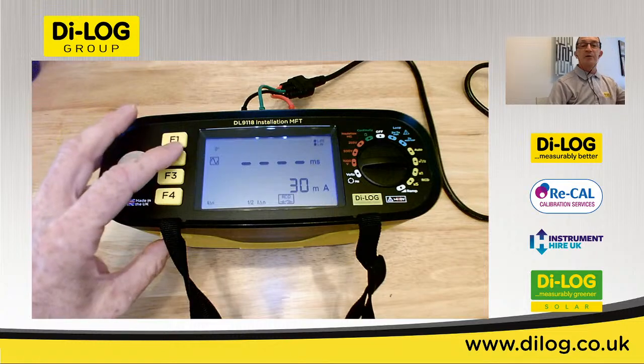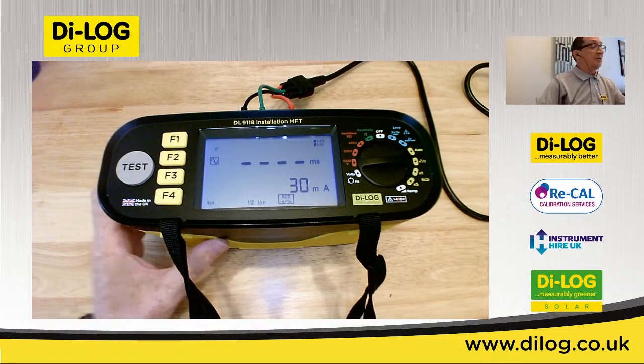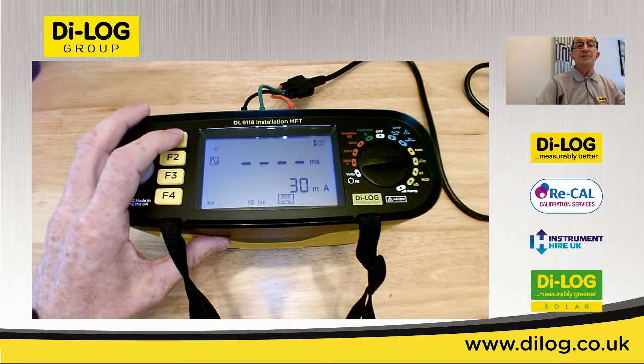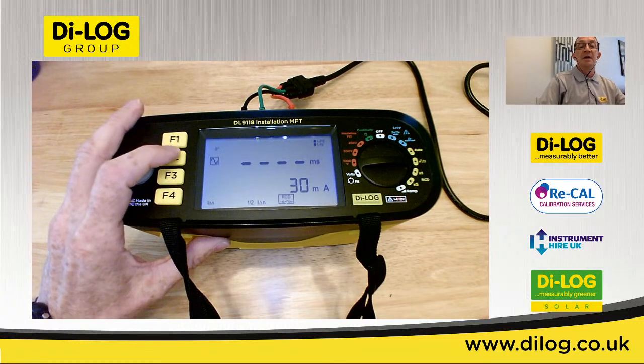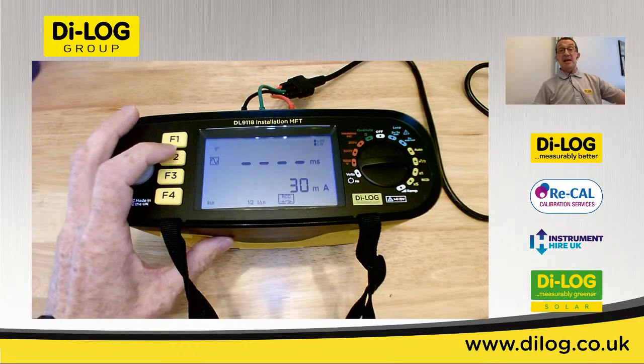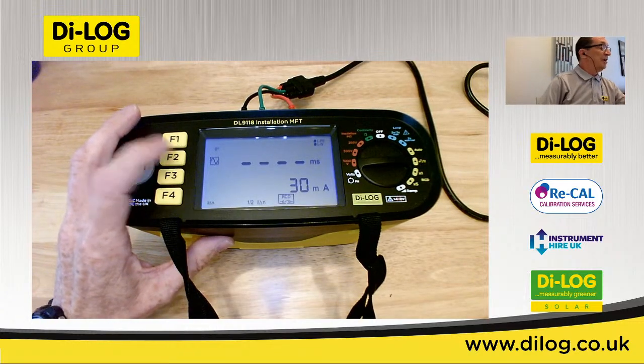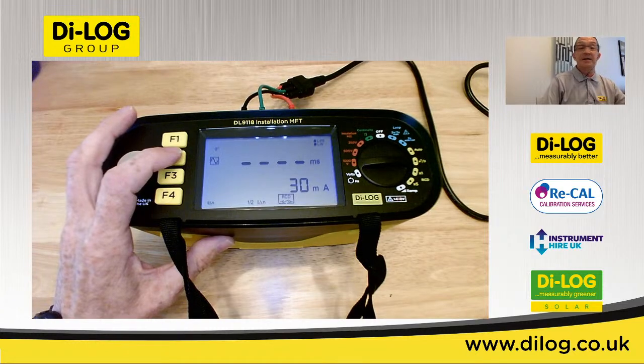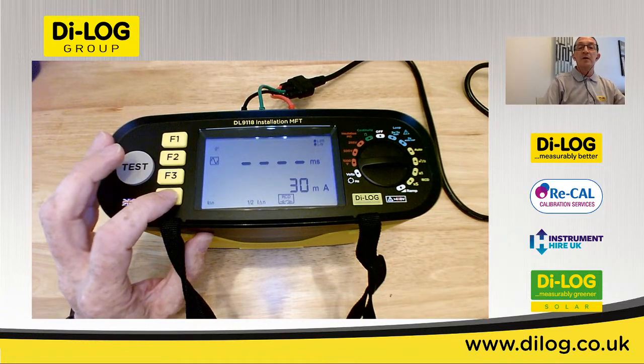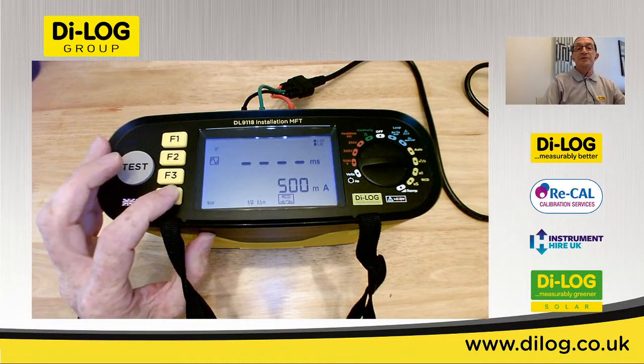On the left hand side we've got a couple of options when it comes to RCD testing. Function 1 changes between the 0 and the 180 phase, and function 2 changes between the type of RCD that we're testing. So here we've got a normal AC RCD, and function 4 would change the size of the trip that I'm testing.